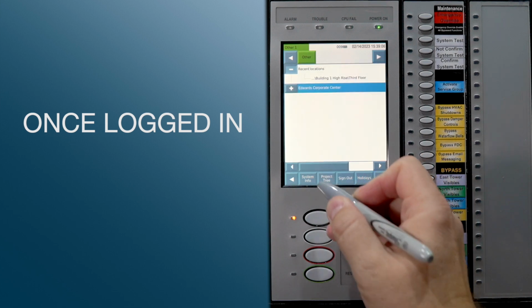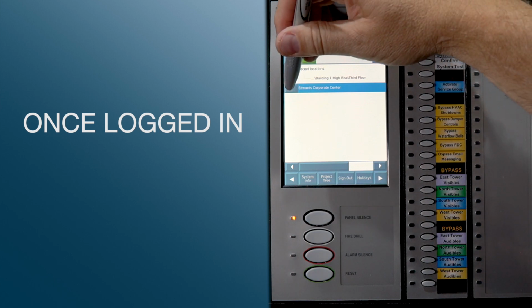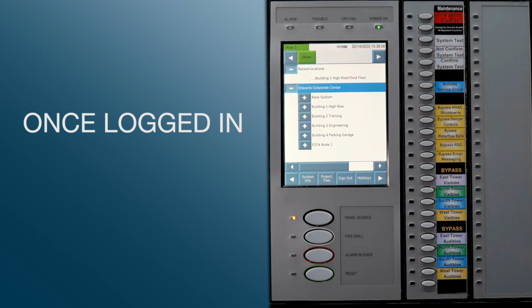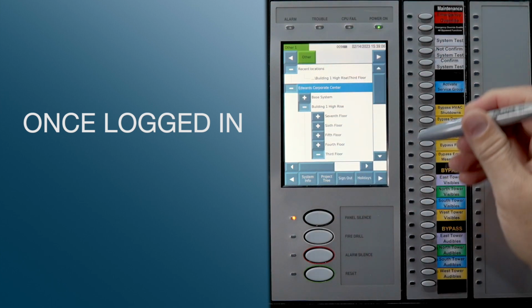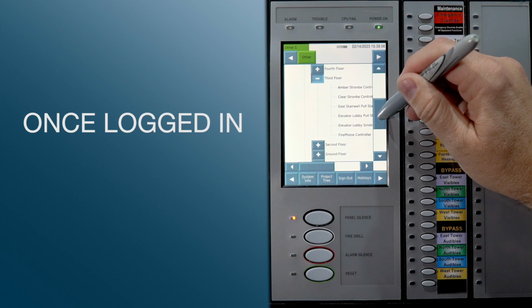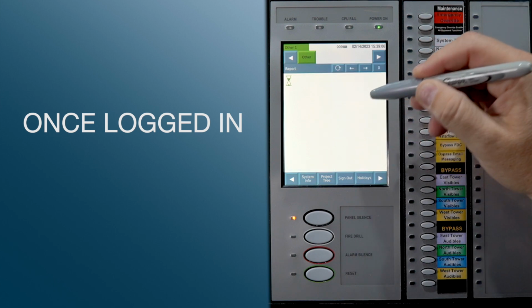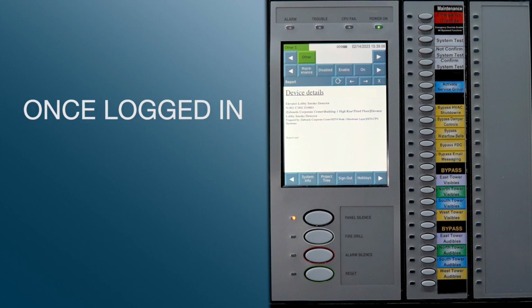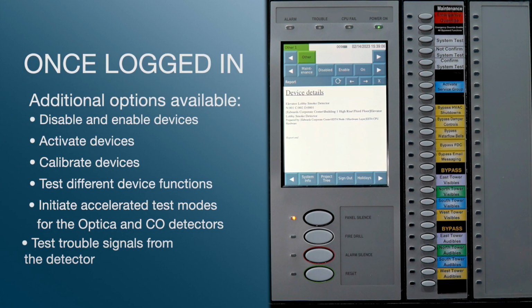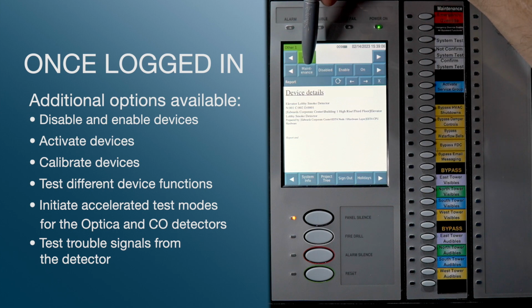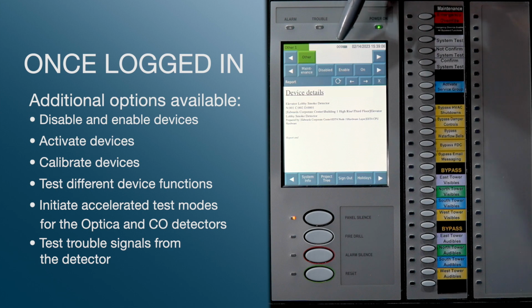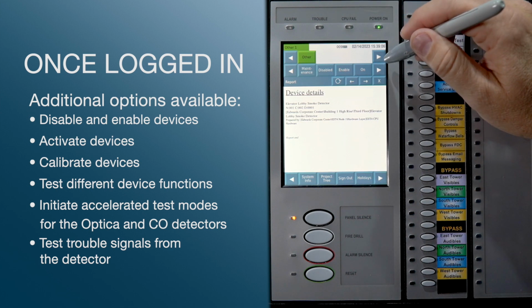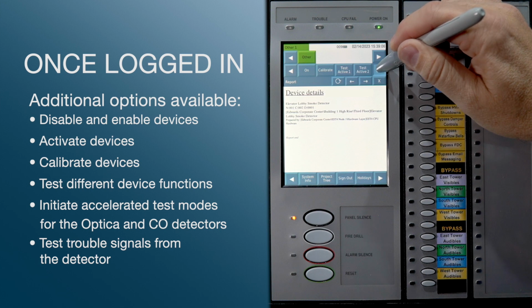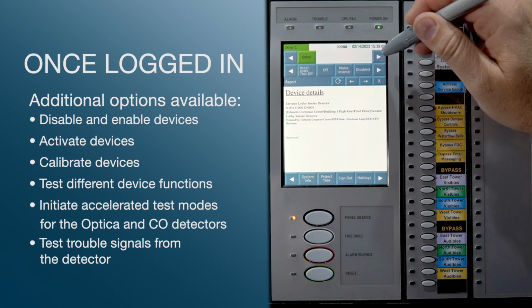Now when I go to the project tree, I expand out the project tree, go to the high-rise building, go to the 3rd floor, scroll down to the device I'm looking for, the elevator lobby smoke detector. Now I'm showing the same information that we had before. I still have the ability to pull up the maintenance screen, but in addition, I have many more options. There's disable, enable, on, and then several other screens of optional buttons.